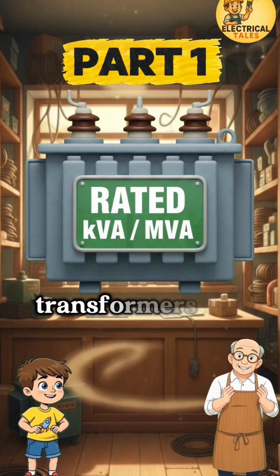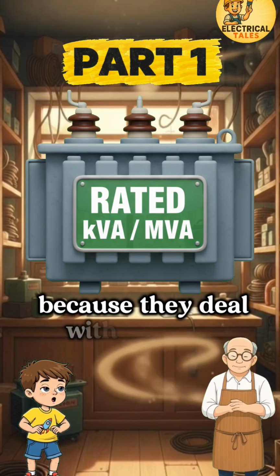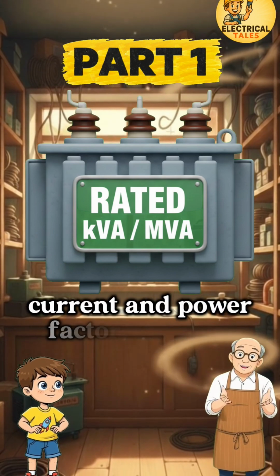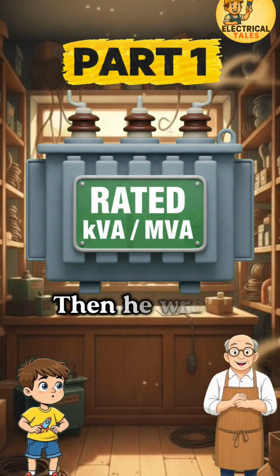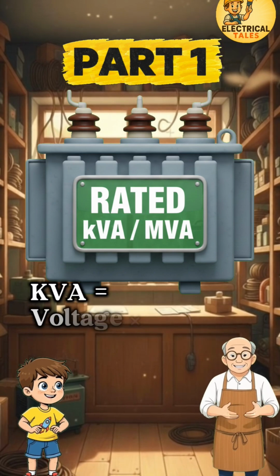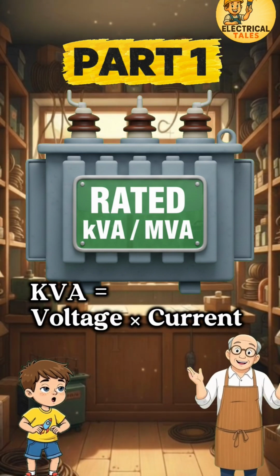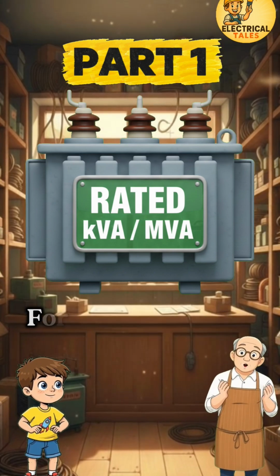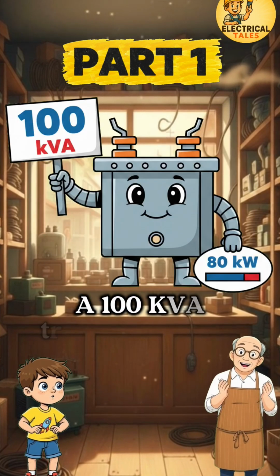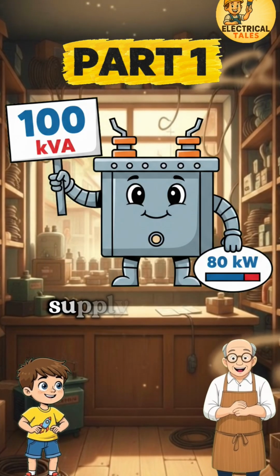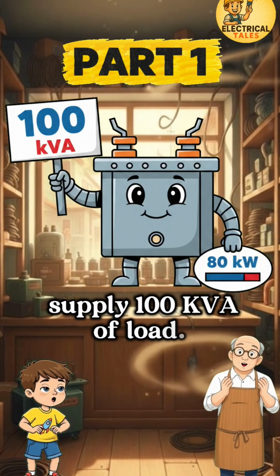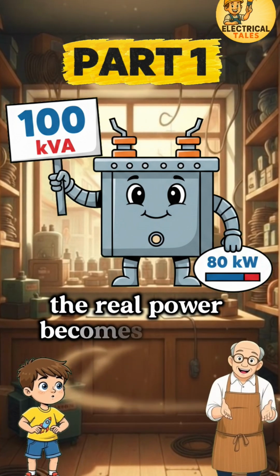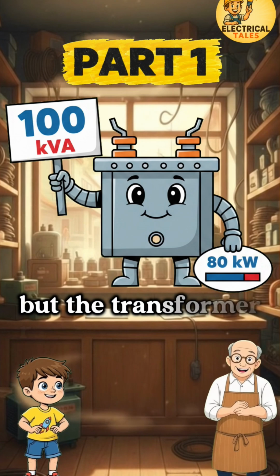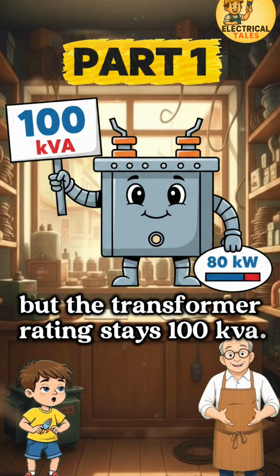He added, 'Transformers use apparent power because they deal with voltage, current, and power factor together.' Then he wrote the formula: kVA equals voltage times current, divided by 1000. For clarity, he said a 100 kVA transformer can supply 100 kVA of load. If the power factor is 0.8, the real power becomes 80 kilowatts, but the transformer rating stays 100 kVA.